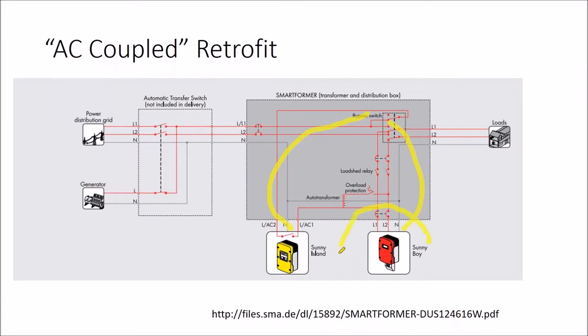What's interesting is the batteryless inverters are rated to shut down when there's a grid failure, and the battery inverter is smarter than the batteryless inverter. It's kind of like a master-slave relationship where the battery inverter is driving the batteryless inverter. And if they're the same brand, they'll actually communicate with each other. In the SMA product line, it can actually detect the loads of the home and then dial up and dial back the solar array based off the loads of the home.